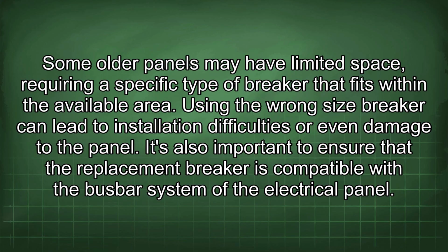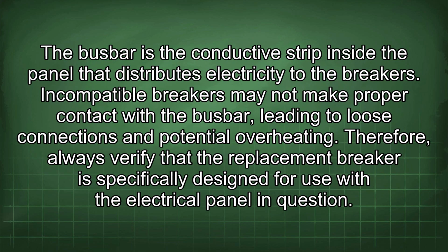It's also important to ensure that the replacement breaker is compatible with the busbar system of the electrical panel. The busbar is the conductive strip inside the panel that distributes electricity to the breakers. Incompatible breakers may not make proper contact with the busbar, leading to loose connections and potential overheating. Therefore, always verify that the replacement breaker is specifically designed for use with the electrical panel in question.